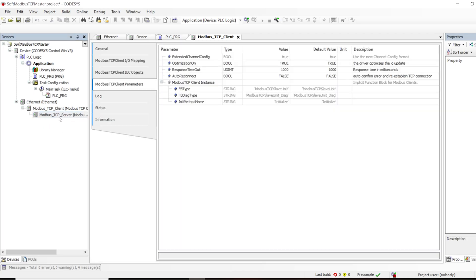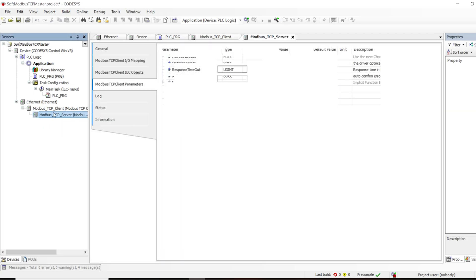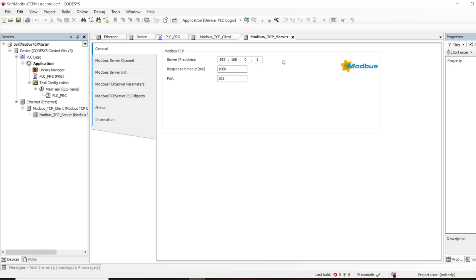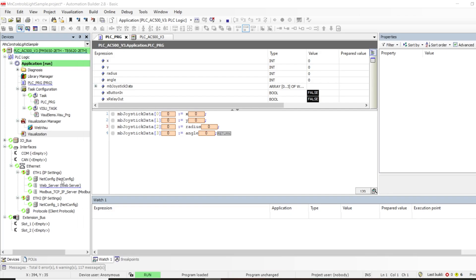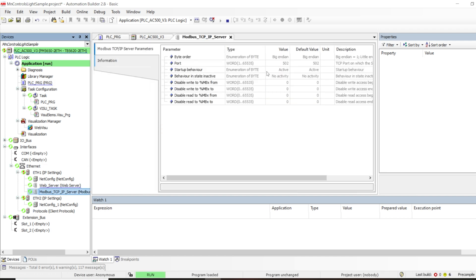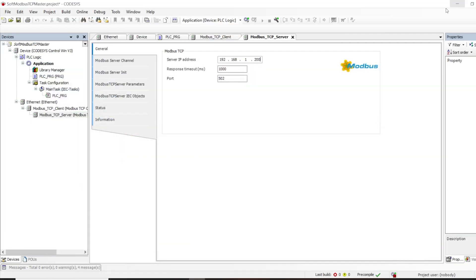Now configure the properties of that server node — double-click on it. The first thing you need is the IP address of the server; my controller's address is 192.168.1.200. You also need the port — on my server it's configured as 502, which is the standard Modbus TCP port. Enter the IP address and port 502 here, and I'll leave the response time at 1000. That's the connection properties configured.